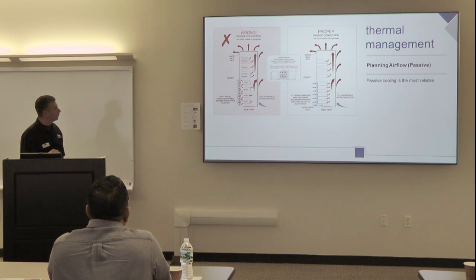So there's the wrong way to do it. As you can see, what's happening here is there are vent panels in between. This equipment has fans in the front, or it's pulling the air in. What happens is it short circuits. Basically the fan's going to pull from the easiest place it can get air. So right now what it's doing is short-circuiting, and none of the cool air is going to be able to get in. So with this, we just basically took the same units and closed the gaps, or you can put a blank panel in between.